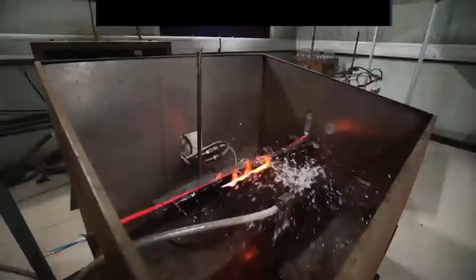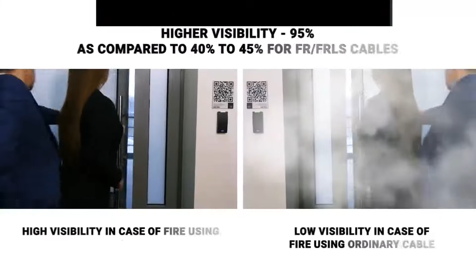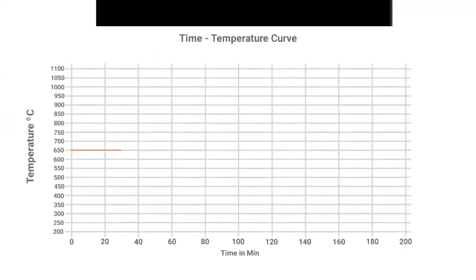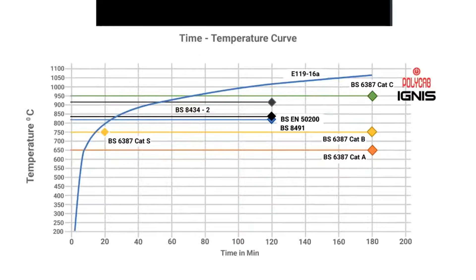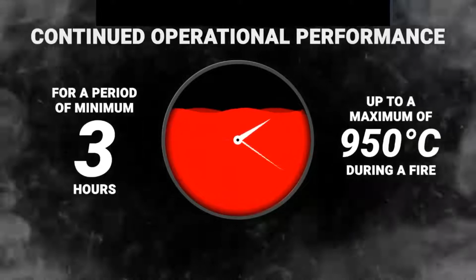The Polycab IGNIS lowers the smoke opacity and gas emissions, prevents flame from spreading, and reduces heat release, making it a low fire hazard. By doing this, it reduces the possibility of deaths due to suffocation. Polycab IGNIS complies with various specifications described under the time temperature curve for the standard fire endurance tests, meeting the standards specified by BS and IEC. It can maintain the power circuit integrity and keep it running for a minimum of up to 3 hours at a maximum temperature of 950 degrees Celsius, making it highly fire resistant. Polycab IGNIS is a must for critical applications like fire alarm systems, sprinklers, emergency lighting, elevators, and PA systems. This keeps the building operational during a fire event, allowing precious time for people to evacuate.